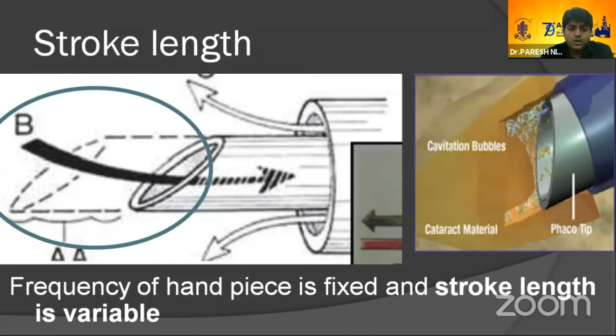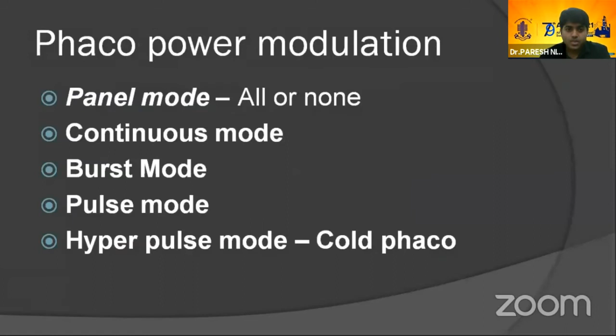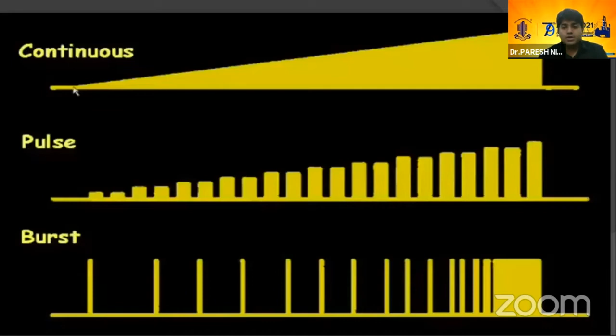The energy is basically calculated with the stroke length. Stroke length is the amplitude of the movement of the phaco tip. The higher the energy, the higher will be the back and forth movement. Now coming to the phaco power modulation, basically there are three phaco power modulations being used.